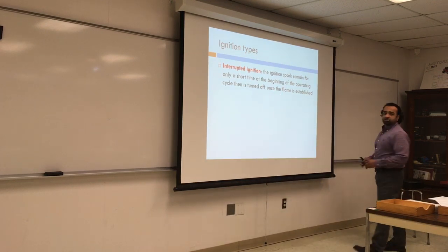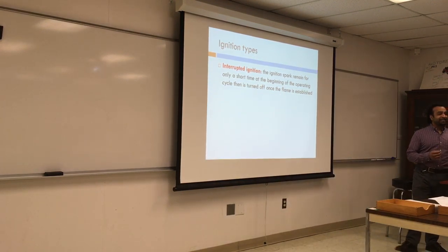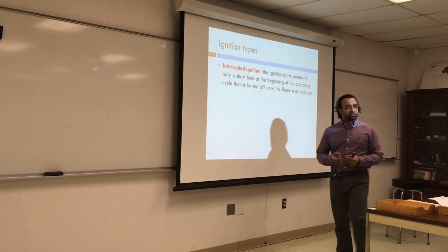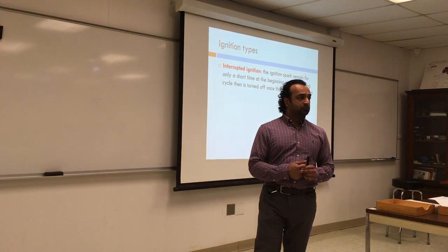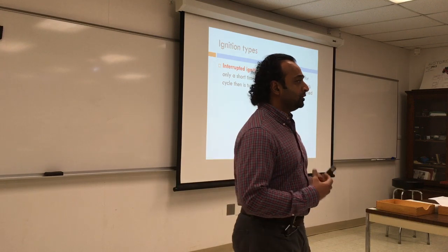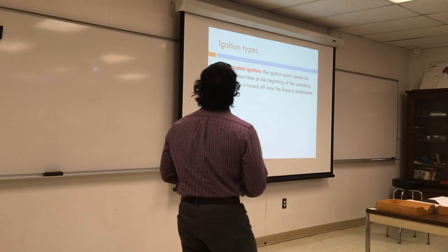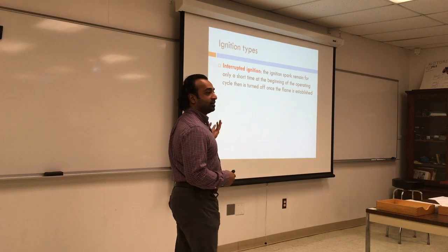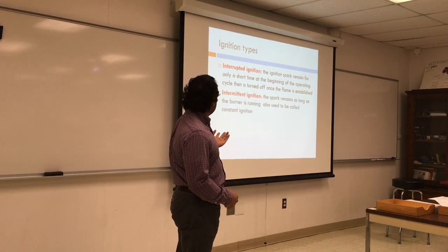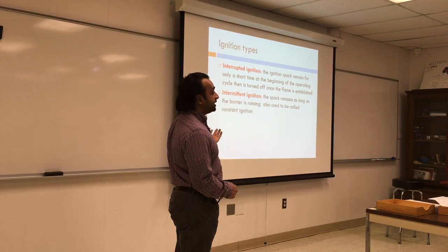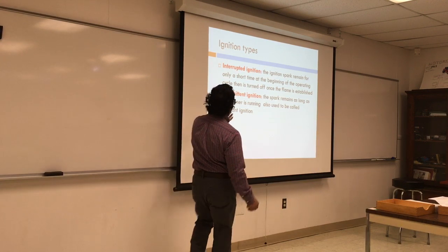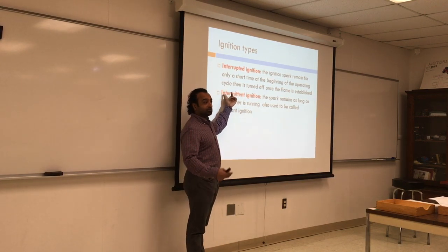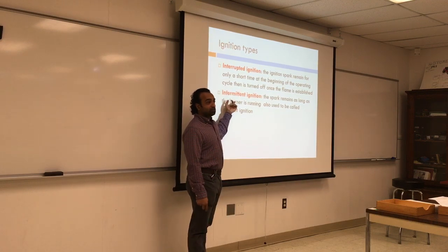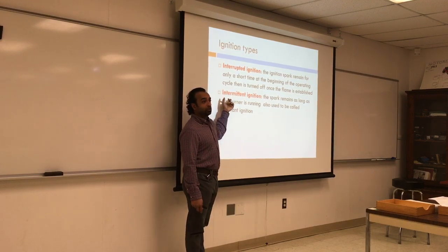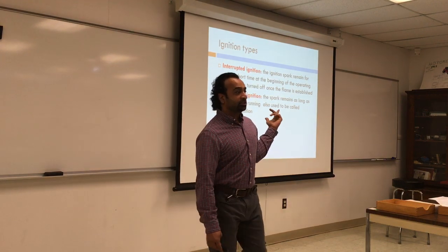The first one is the interrupted ignition. The ignition sparks for a very short time. Once the CAD cell sees the flame, it will cut off the ignition. It means that we have proven the flame. No need for continuous ignition. That's called interrupted, even though it doesn't sound like it. Interrupted means it will go away. Intermittent, even though it sounds like it means not continuous, is continuous. So be aware of those two words because they will come up in the oil burner exam.